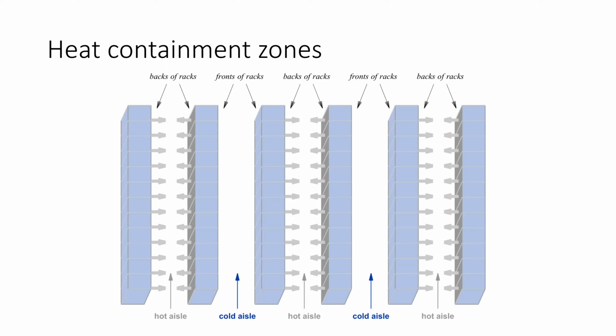Because servers pull cold air from one side and release hot air on the other side, operators align servers in racks so that cold air comes from one side and is released on the other, for all servers on the rack and all racks in the row. Basically, we're going to have these hot aisles with hot air coming from both sides, and cold aisles with cool air on the aisle, and then the servers pull in the cold air from this aisle and release hot air on the hot aisle.